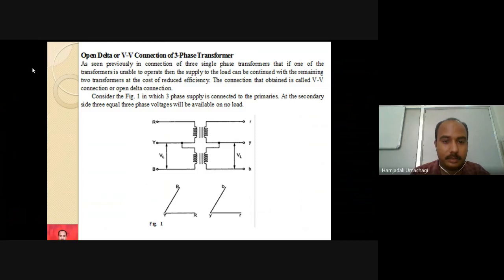Dear students, today let us see another type of three-phase transformer connection, that is open delta or VV connection of three-phase transformer. As seen previously in three-phase connection of three single-phase transformers, if one of the transformers is unable to operate, then the supply to the load can be continued with the remaining two transformers at the cost of reduced efficiency. The connection that is obtained is called VV connection or open delta connection.